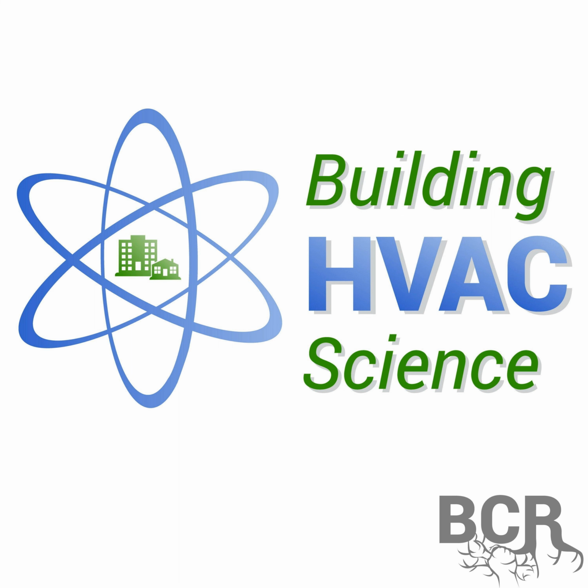So that's going to jack up your number. And don't forget to account for any kind of things like a bypass humidifier. Again, don't let that sneaky air get by you. All the air has to be accounted for when you're taking this bulk measurement. So now what do you do with this temperature number you have? Oh, hang on a second.